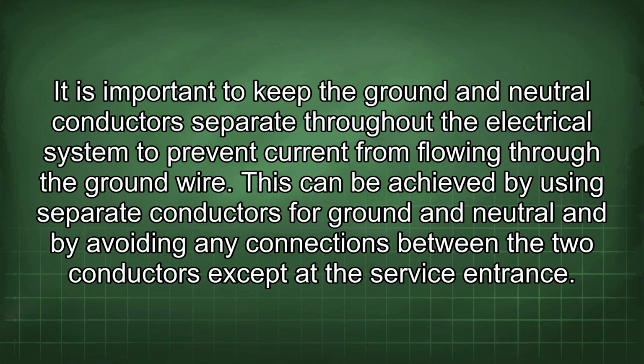It is important to keep the ground and neutral conductors separate throughout the electrical system to prevent current from flowing through the ground wire. This can be achieved by using separate conductors for ground and neutral and by avoiding any connections between the two conductors except at the service entrance.